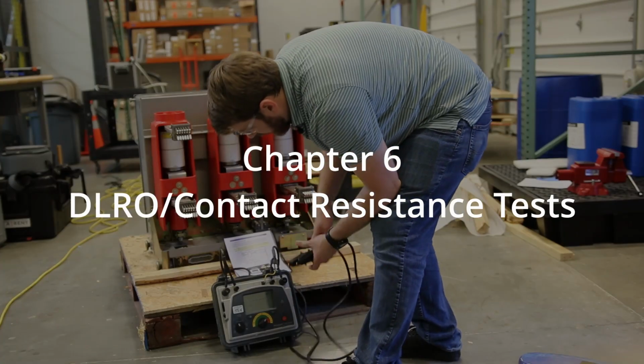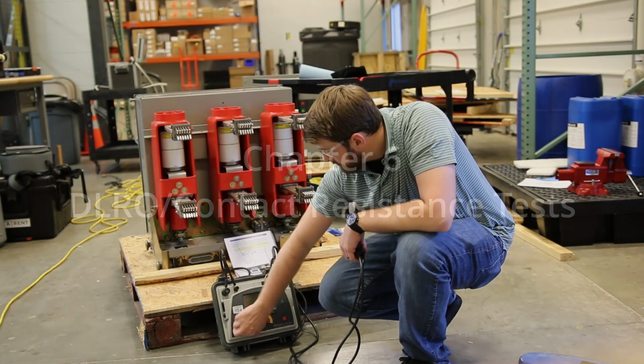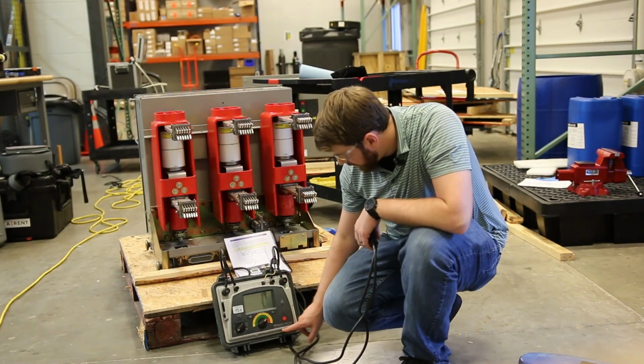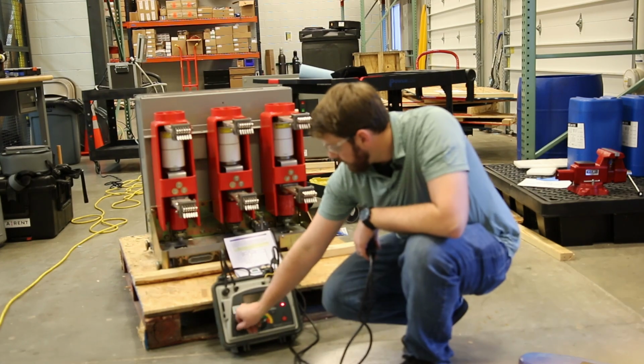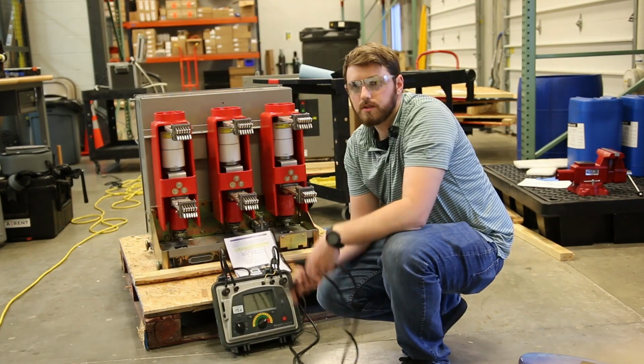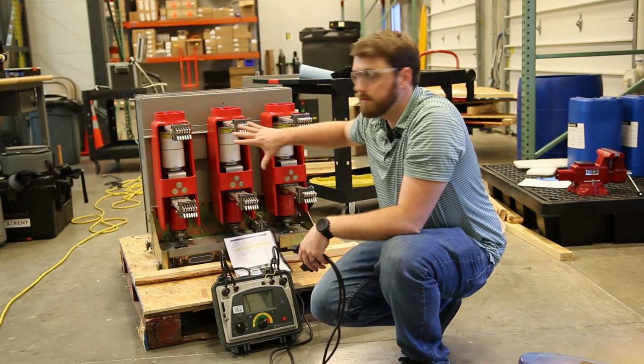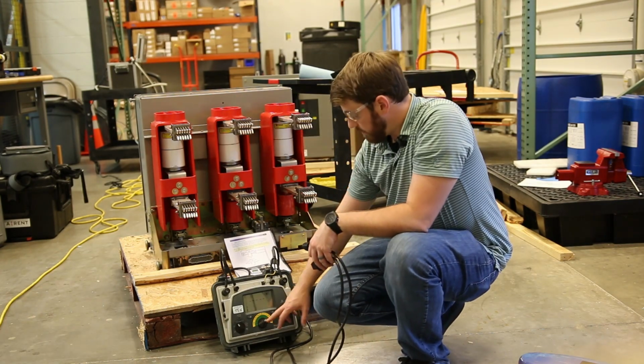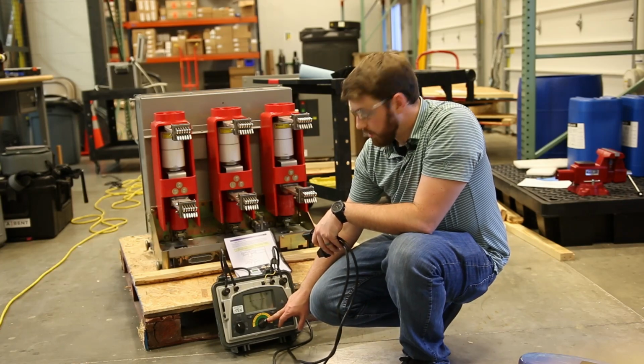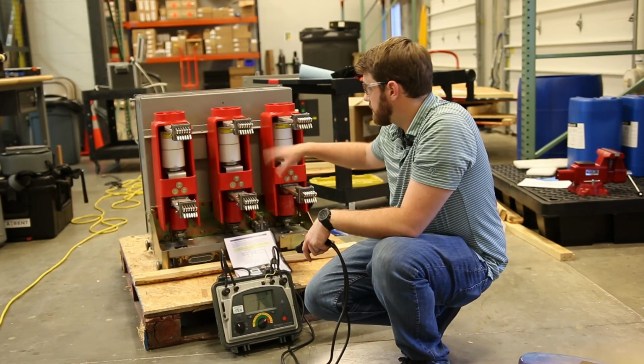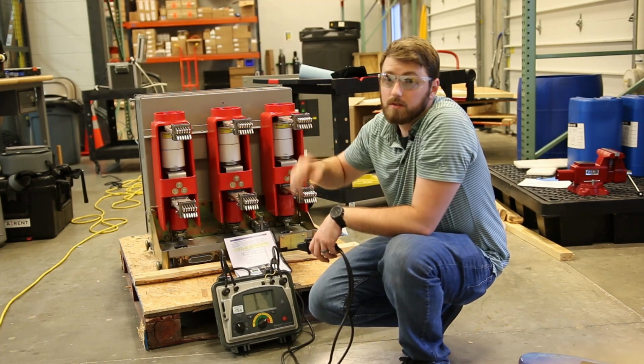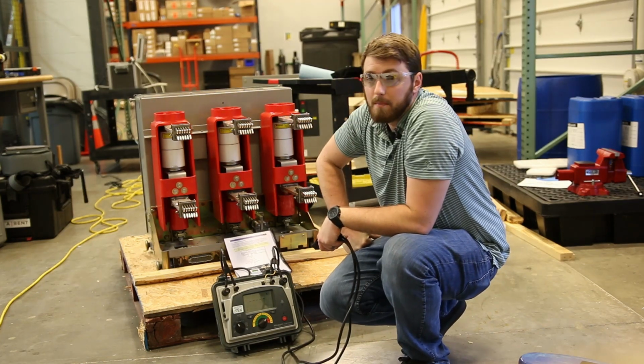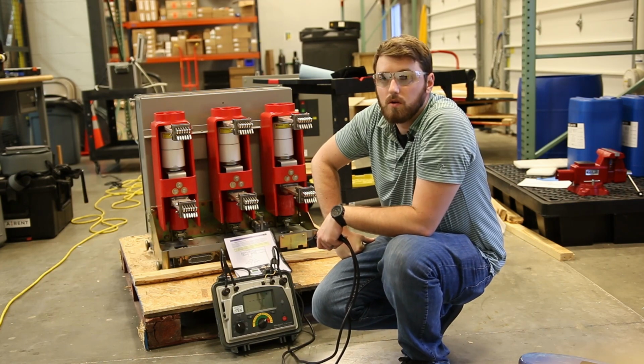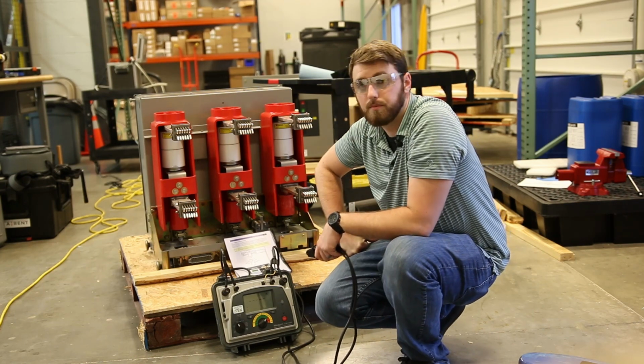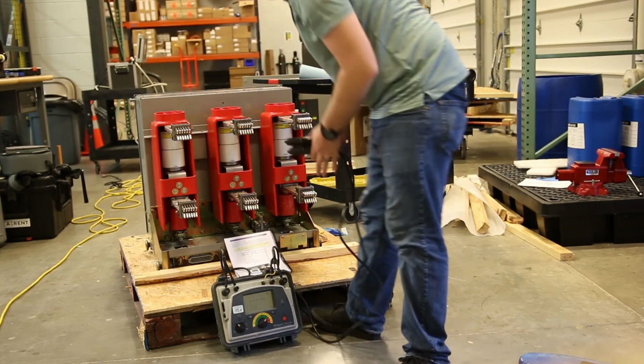All right, I don't know how well y'all are gonna be able to see this. These test sets have a couple different modes. This is the Megger DLRO 10 HD. I'm gonna set this to auto, which as soon as these make contact, it starts pushing current. We're on the 10 amp range. Obviously we're looking for the lowest amount of resistance possible because I'm expecting these contacts to be in a really good condition. Per the manual, they should be below 50 micro ohms. So yeah, start pushing some current through and see what we get.